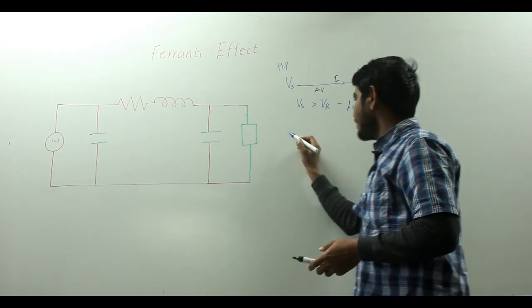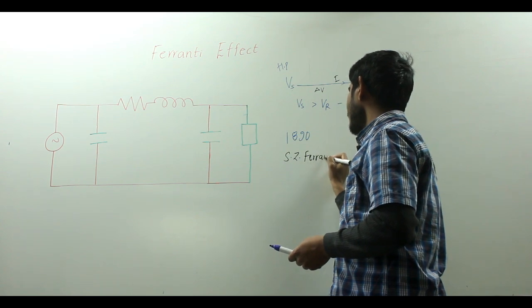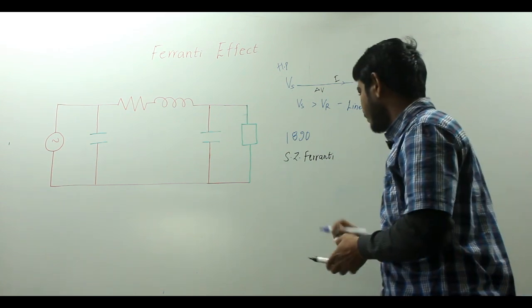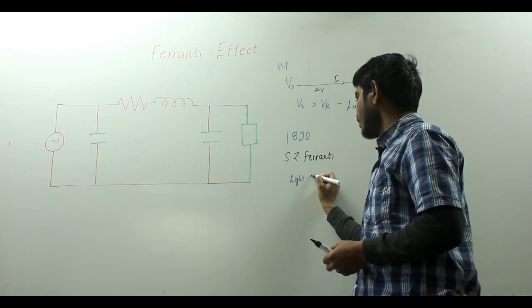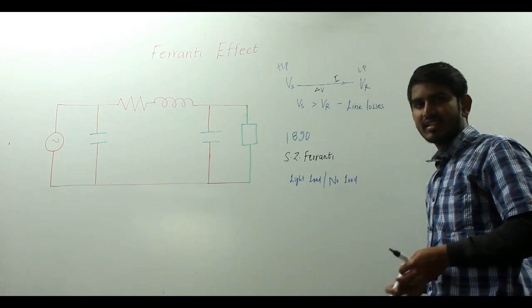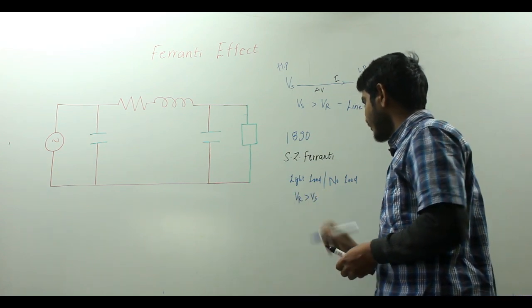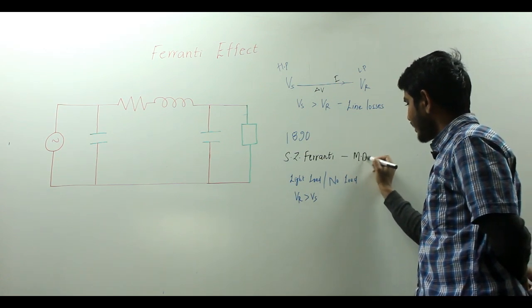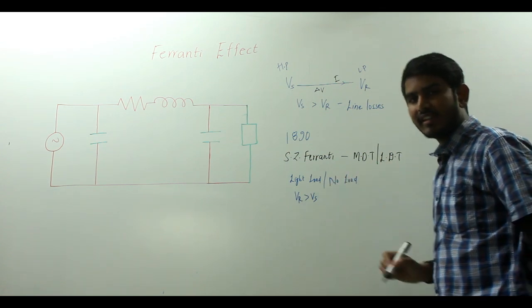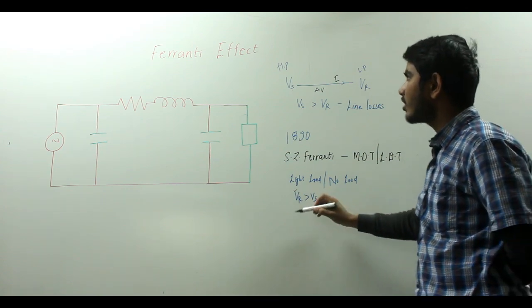But in the year 1890, Sir S.Z. Ferranti came with an astonishing and surprising theory suggesting that in case of light loading or no load at the receiving end, in medium distance and long distance transmission lines, you witness the receiving end voltage to be greater than the sending end voltage — a phenomenon known as the Ferranti effect.